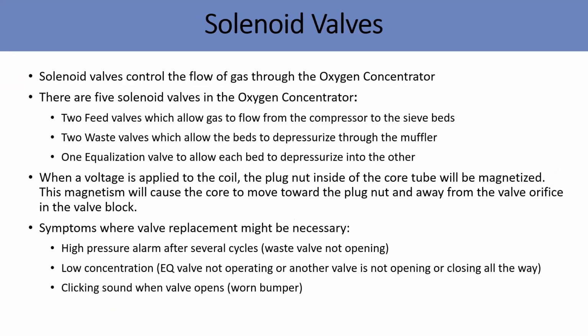Solenoid valve, like I mentioned earlier, you have the high pressure solenoid valve, then the waste solenoid valve and the equalizer valve normally used in your system. If your filtering system is not working properly, sometimes the solenoid valve has failed because some dust or something went into the valve and it doesn't lock properly. That can cause a low flow indication, sometimes high pressure or low pressure on the system. That's one of it. And very important, you have to check the coil. Sometimes the coil breaks and the solenoid valve is not going to work. So you need to look into that particular solenoid valve. Then the O-ring of the solenoid valve, sometimes wear and tear will break as well.